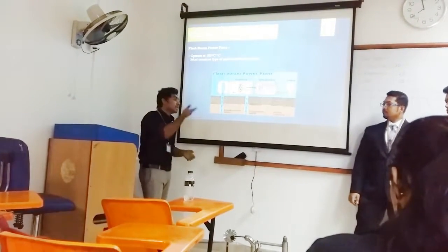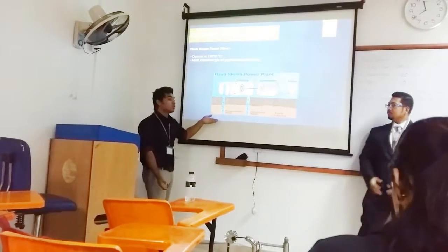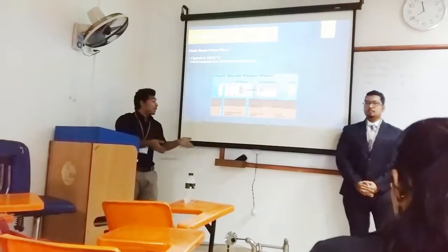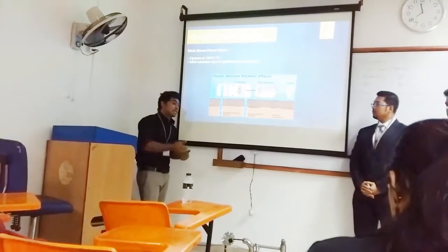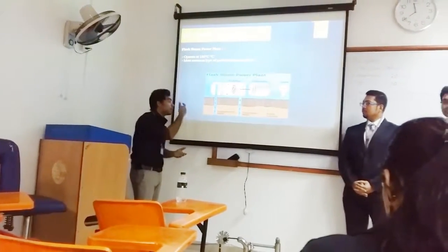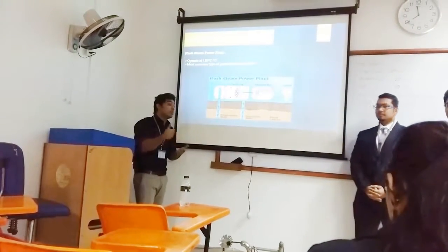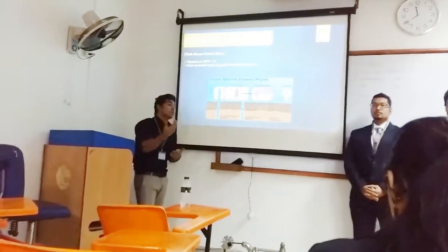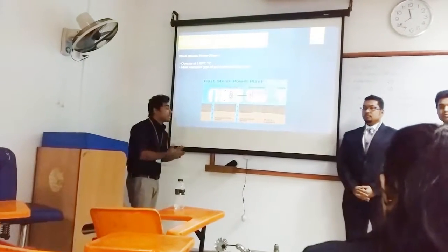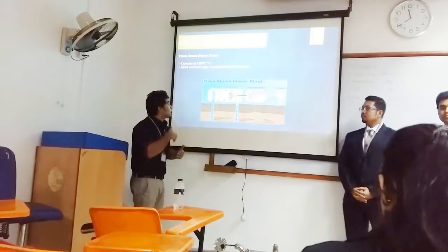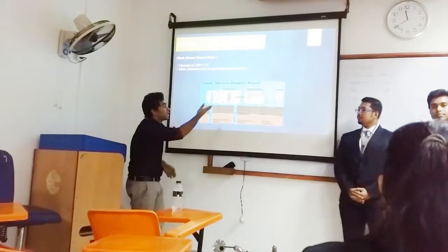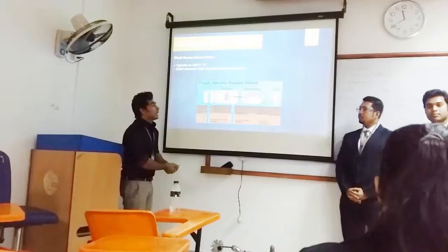As the water comes from deep underground in the upward direction, the pressure gradually decreases. This decrease of pressure causes some of the hot water to convert into steam, and this steam is separated using a special methodology, and the steam is directed to the turbine, and the turbine is connected to the generator. The generator is connected to the load.